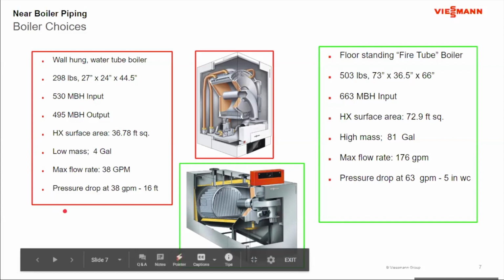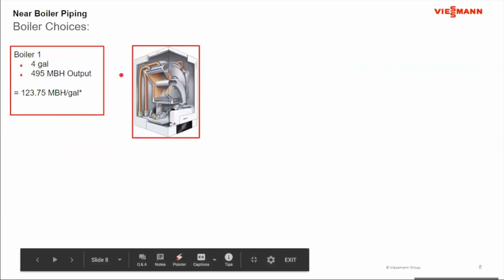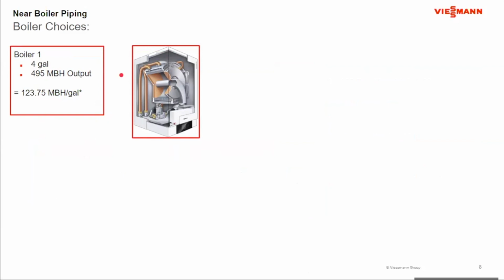So for this wall-hung boiler, I'm going to concentrate on two characteristics of the boiler in this discussion. Here we're looking at the gallons of water and the output of the boiler. What we're really trying to look at is how many thousands of BTUs per gallon of water inside that boiler do we have? If I take the 495,000 BTUs and divide that by 4 gallons, that tells me that in this boiler, I have 123,750 BTUs per gallon of water, okay?